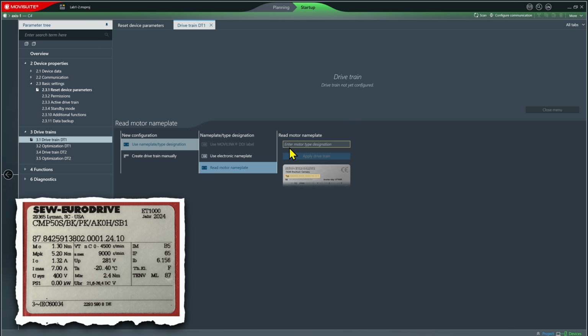So here's what my motor's nameplate looks like, and I can see the key information here. All that I really need to enter is the motor model and size, whether it has a brake or not, whether it has a temperature sensor, and whether it has an encoder. You can skip things like connector nomenclature and flange nomenclature and gearbox nomenclature. That's unimportant at this point. So we'll just go ahead and type this in.